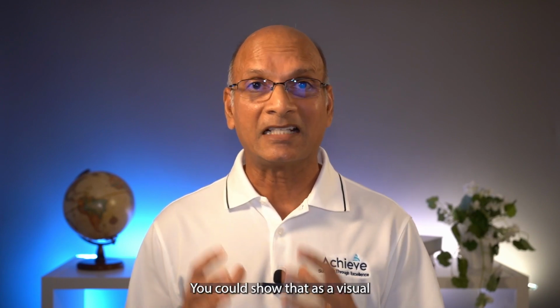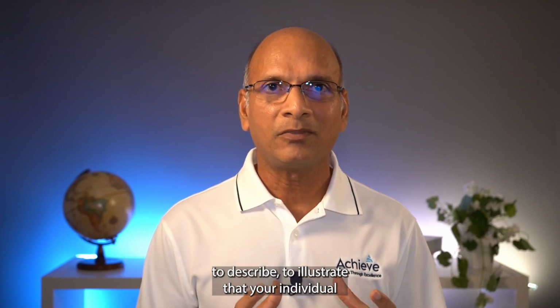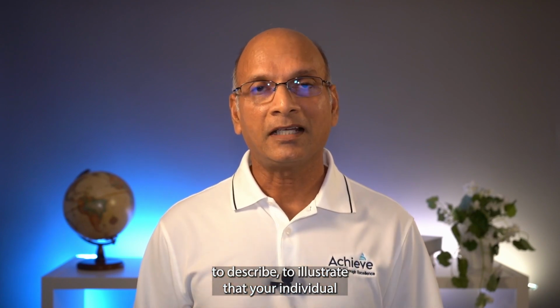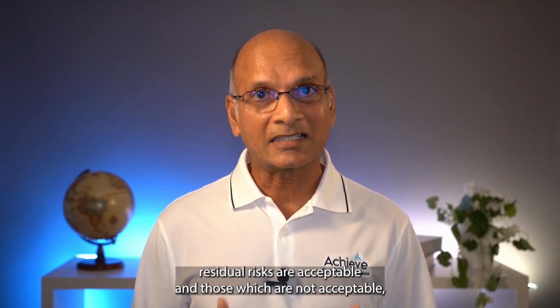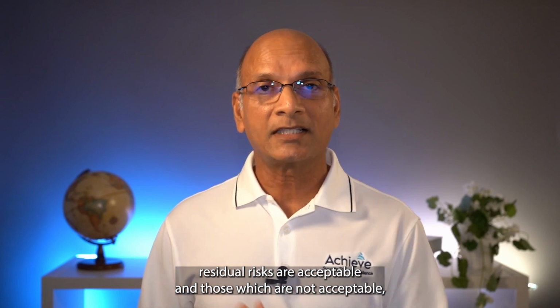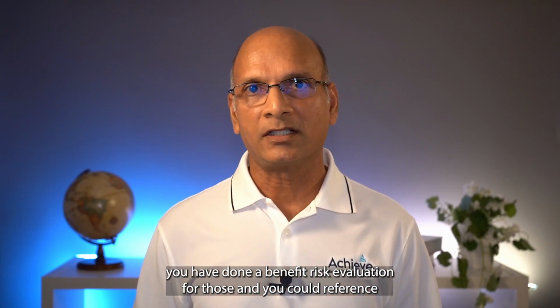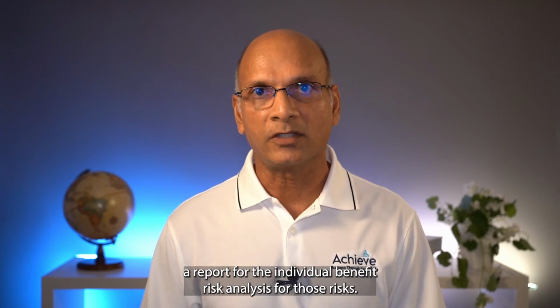You could show that as a visual to illustrate that your individual residual risks are acceptable, and for those which are not acceptable, you have done a benefit-risk evaluation, and you could reference a report for the individual benefit-risk analysis for those risks.